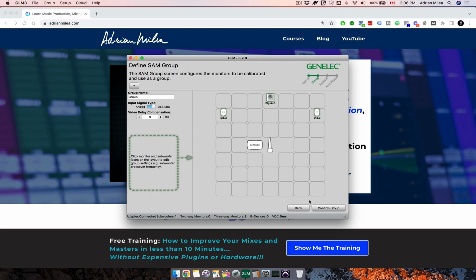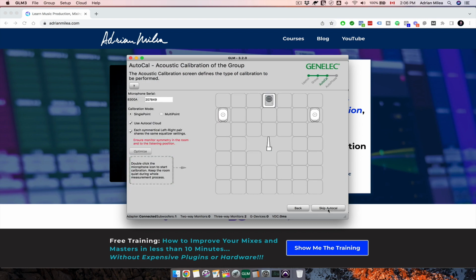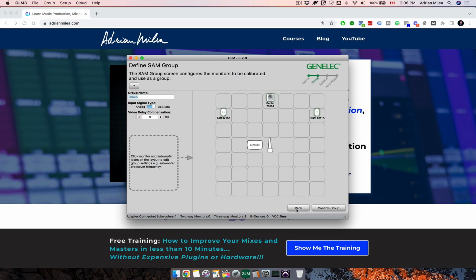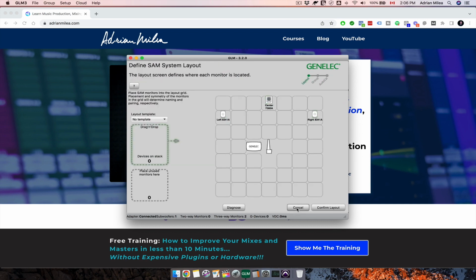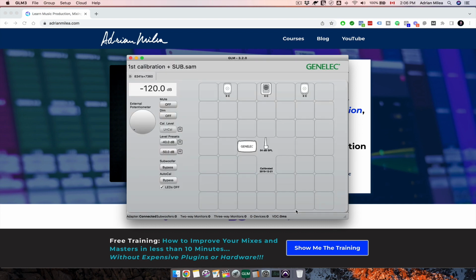After you're happy with your setup, confirm group, and then it's time for the actual calibration. You can choose between single point or multi-point calibration mode. I usually use a single point calibration mode, and until now I'm happy with it. And I'm not going to calibrate my system now, but in your case you'll have to just follow the steps. After the calibration is finished, next to the group name you have selected, you'll see the letter D for digital. And that is if you selected the AES/EBU option I was talking about earlier.